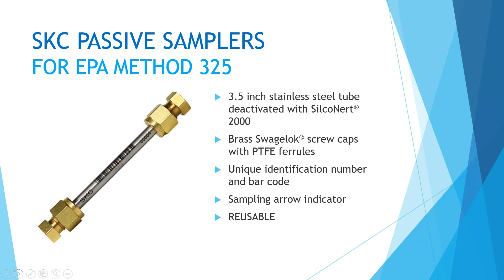As you may know, SKC has previously developed a passive sampling badge called the Ultra, which has the option of thermal desorption analysis by transferring the sorbent from the badge to a thermal desorption tube. Now, the larger area, the face, if you will, of the Ultra sampler is much bigger than the little face of a tube. So it has a much higher uptake rate of 16 milliliters per minute for benzene, compared to 0.67 milliliters per minute for benzene using the passive tube. Again, 16 milliliters a minute compared to 0.67.